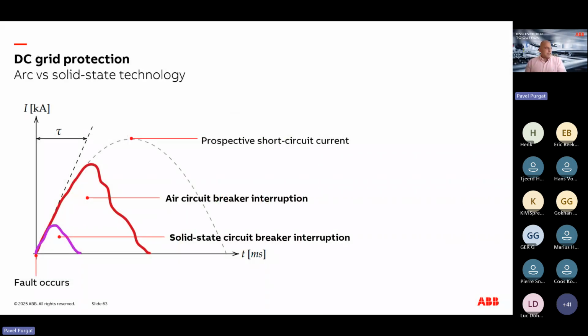Now, the advantage of using a semiconductor as a current interrupting device is the limitation of the energy. So here we see, and this is of course just a qualitative illustration, that we have a prospective current; an air circuit breaker will take some time, and even though it's current limiting, it takes too long. And then we introduce solid-state circuit breakers that take just a fraction of the entire time and release just a fraction of the energy.